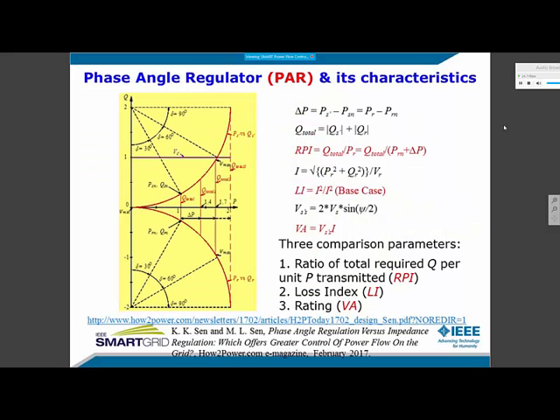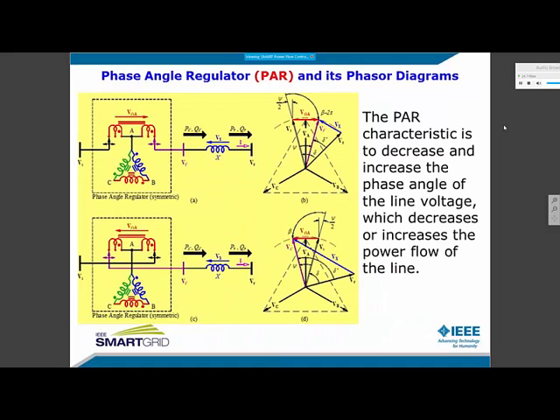Now, I chose three arbitrary operating cases. They are 40%, 70%, and 100%. The P-flow enhancement of a power increases the reactive power flow in the line. It shows that the load is burdened with the responsibility of supplying a higher amount of Q as the P demand increases. The transmission line owner does not prefer to operate the phase angle regulator at a higher P value due to the penalty of higher Q flow in terms of higher losses in the line, which, by the way, contributes to additional global warming.